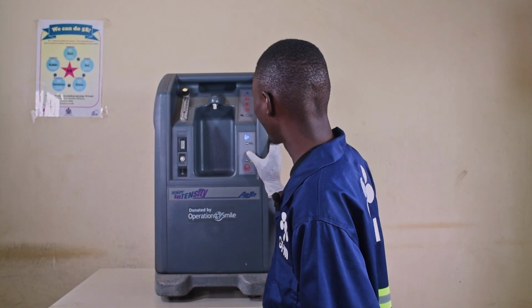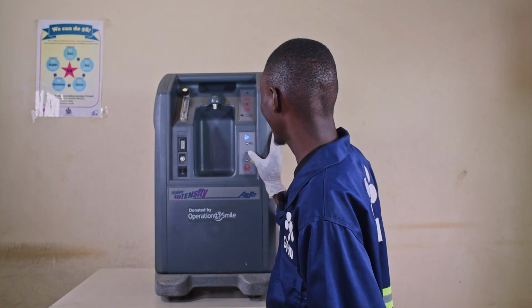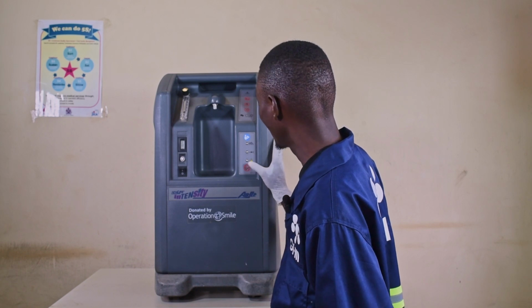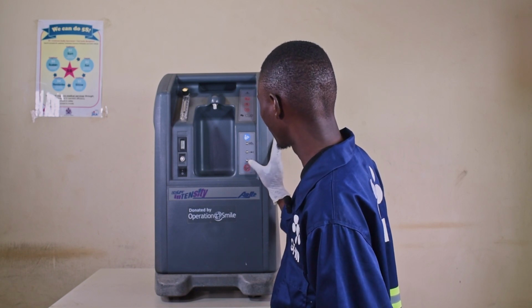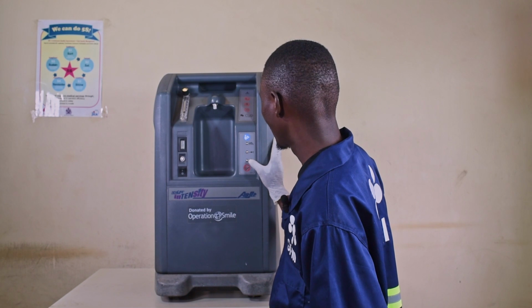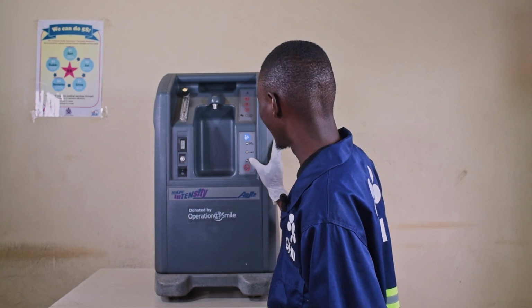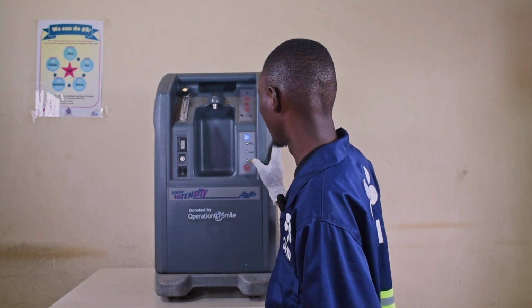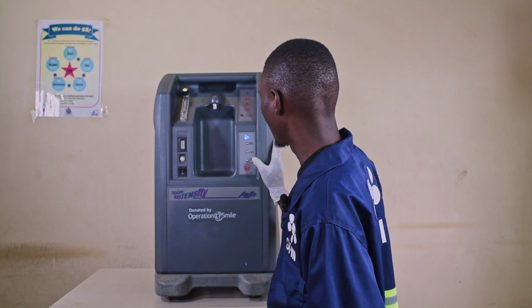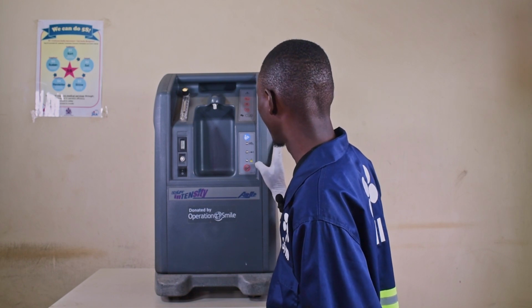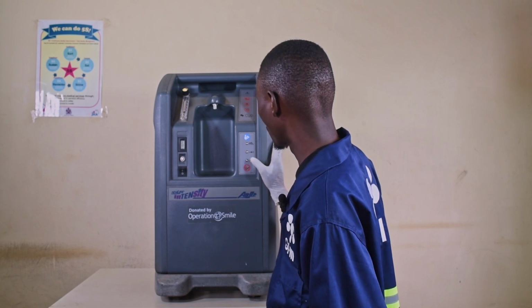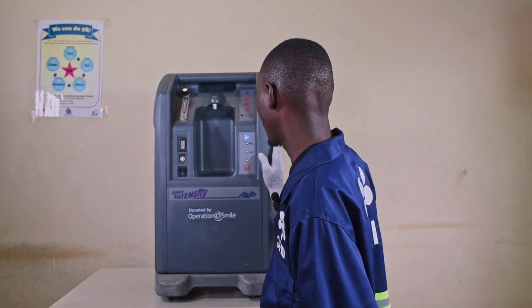On the middle, we have the power indicator. This indicator turns green when the unit is switched on. Lastly, on the bottom, we have the service indicator. This indicator turns red when there is a malfunction within the unit. For example, when there is flow obstruction, a high output pressure, low output pressure, or compressor failure.